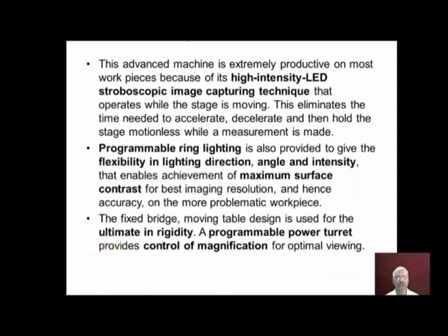This advanced machine is extremely productive on most workpieces because of its high intensity LED stroboscopic image capturing technique that operates while the stage is moving. That means when the stage is moving along with the workpiece, the measurement is possible. We need not stop the table for making the measurement. Programmable ring lighting is also provided to give flexibility in lighting direction, angle and intensity, which enables achievement of maximum surface contrast for best imaging resolution and hence accuracy on the more problematic workpiece.